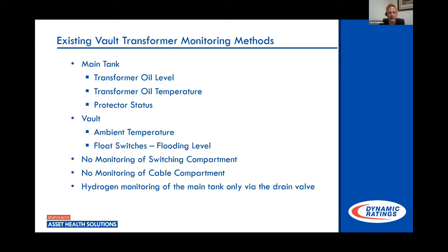But what you're not seeing a lot is people aren't doing any monitoring of the switching compartment, any monitoring of these cable compartments. And typically, if they're doing any kind of monitoring that would provide an indication of problems occurring within the main tank of that transformer, it would only be hydrogen monitoring through the drain valve of the main tank. So looking at these temperatures, even bringing in hot spot temperatures, is not really a good indicator that you have a problem, an incipient fault starting to occur. You're not going to see a big swing in the operating temperature that would be noticeable because that heat dissipates so quickly into the oil. And this, again, goes for any transformer, be it a substation transformer or a small distribution transformer.